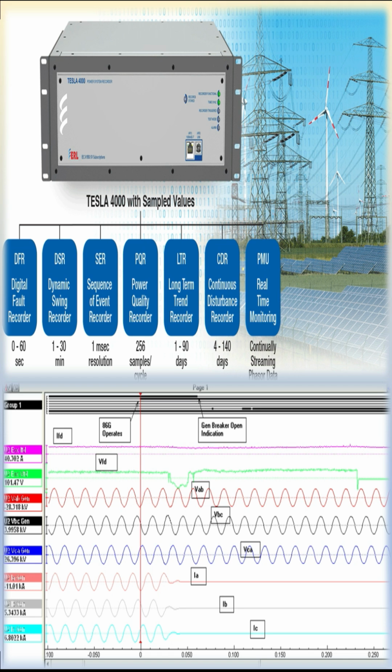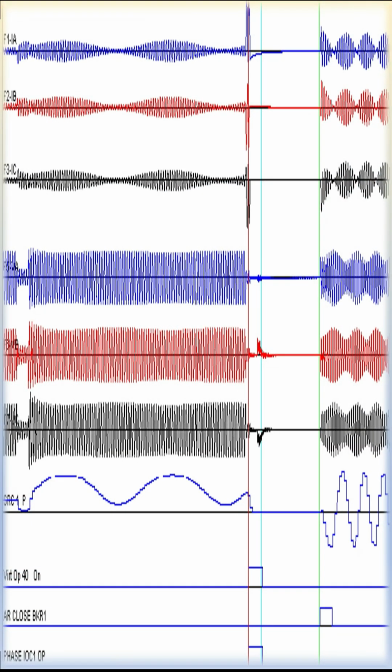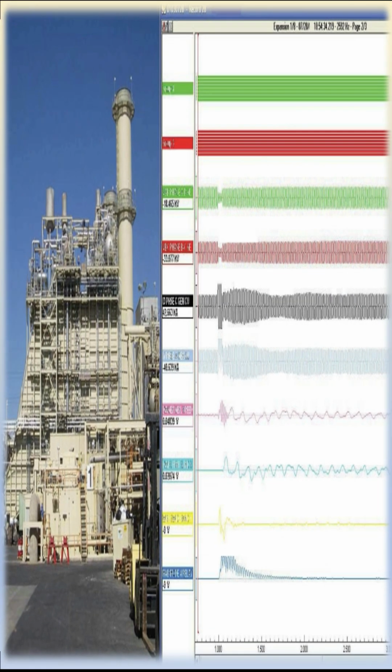A digital fault recorder (DFR) for overhead transmission lines is a sophisticated device that captures system events at high frequencies up to 24 kHz, records dynamic disturbance data, logs sequence of events data, and calculates fault locations. It leverages intelligent electronic device data to investigate disturbances and monitor assets. It can also stream and record continuous oscillography data at 3 kHz.